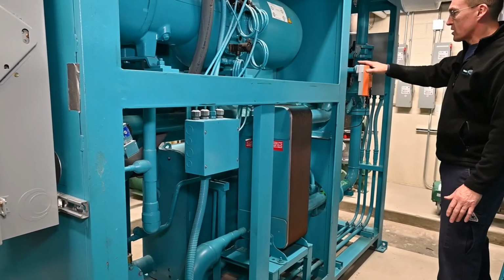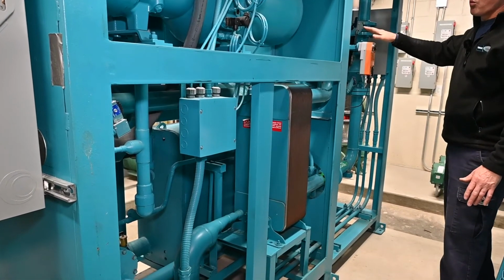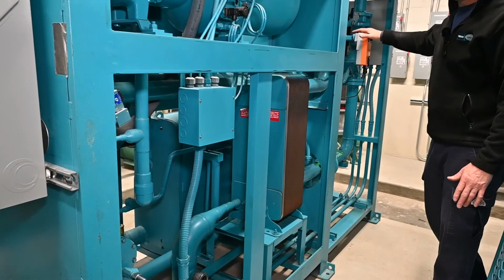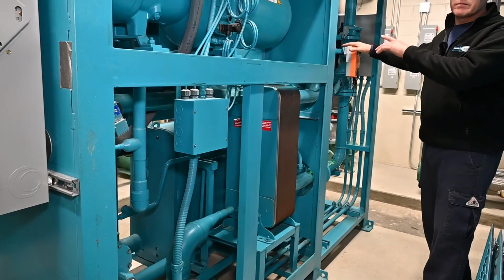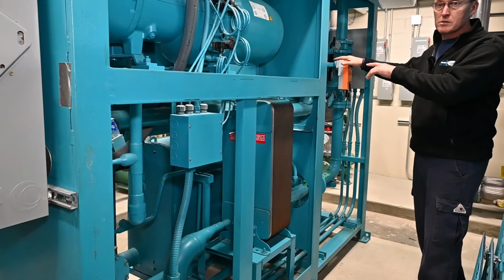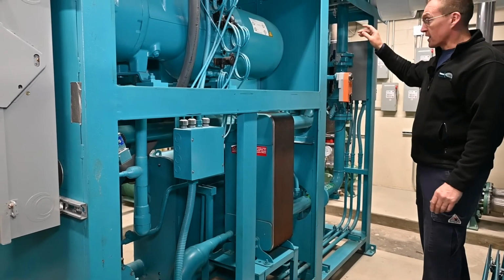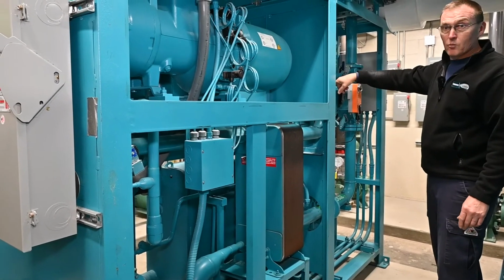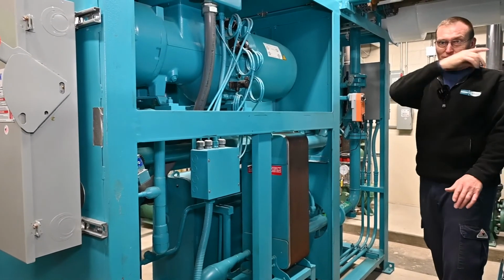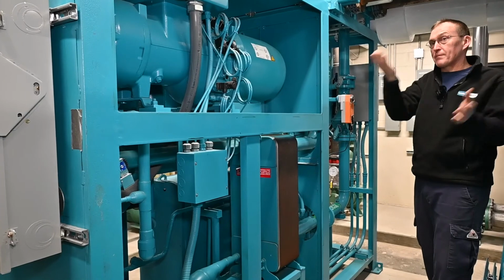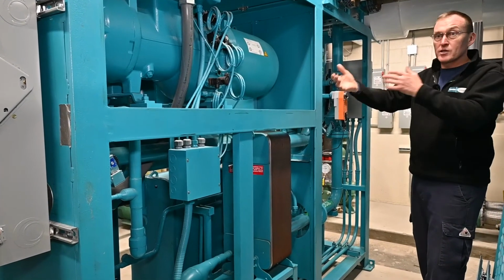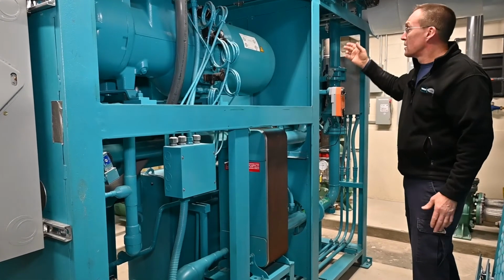And on the warm glycol side, when you get a call for cooling, the pump is going to start. The pump will speed up to 60 hertz. Then you're going to hear GP1, or whichever one if it's compressor 2, because, again, we flip-flop these compressors. We change the rotation every single start time.